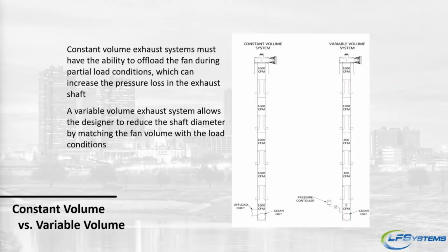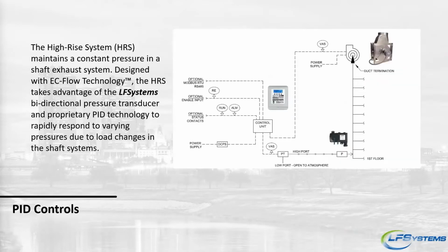And that's where we offer our high-rise exhaust system. The high-rise exhaust maintains a constant pressure and uses our existing technology. Again, if you've joined us for any of our presentations, you've learned about the EC flow technology with our positive and negative control systems. We use basically the same base program for all of our controls, and then we specialize and customize them for the application. For this instance, we use our L150 control. We'll talk about that in a second. It maintains a slight negative here at the base, and then we'll have a fan up here on the roof, varying the speed throughout.